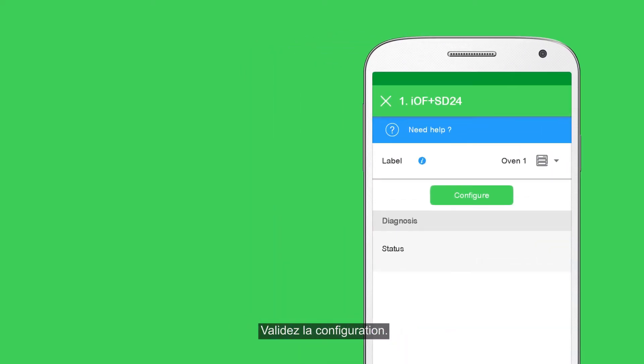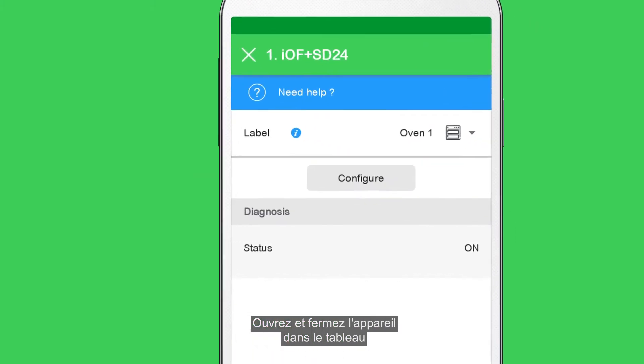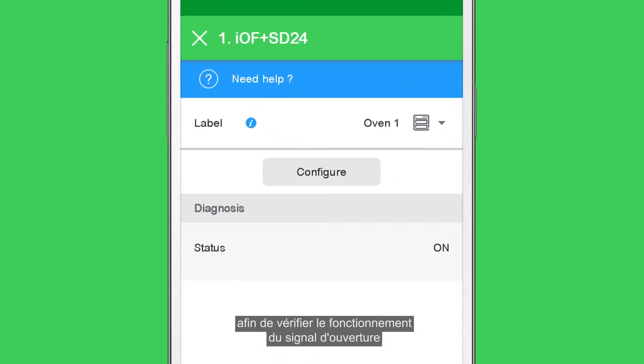Validate the configuration. Open and close the device in the electrical panel to verify that the corresponding status is correctly indicated in the diagnosis section.